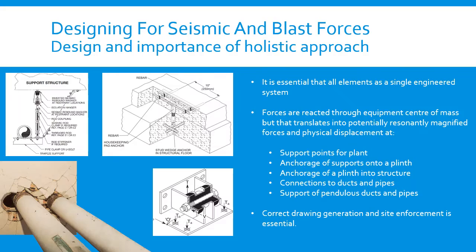Whether statically or dynamically determined, it's important that all elements are considered part of a single engineered system. Some examples are shown on this slide, but in summary is that each element that contributes to a load path needs to be correctly engineered. Anchorage into a concrete plinth requires the plinth to be similarly well anchored to structure. Ducts and pipes hung from above act as natural pendulums.